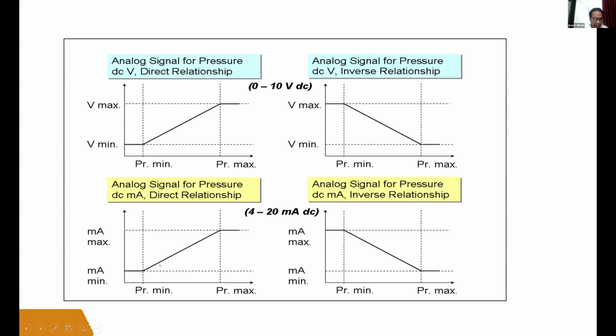You can see here, if the pressure is 0 bar, the sensor will show the minimum value of 4. The sensor I have used here is a 4 to 20 milliamps sensor. It means that it is giving the output in the form of current. So for 0 bar, it will give an output of 4 milliamps, and for 100 bar pressure, it will give an output of 20 milliamps. In the same way, vice versa, I have shown the inverse relationship here.